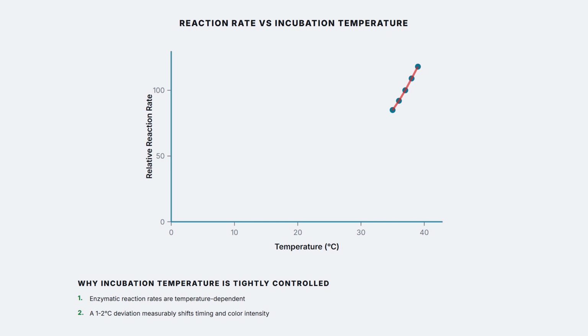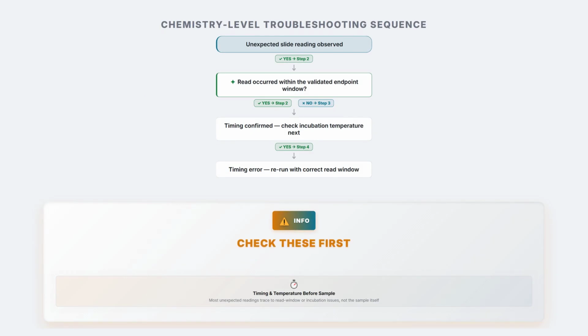Enzymatic reaction rates are temperature dependent, and even a 1 or 2 degree deviation from the validated incubation temperature measurably shifts the reaction's timing and final color intensity. When a slide reading looks unexpectedly off, the chemistry-level troubleshooting sequence starts with timing and temperature before anything else. Confirm the read occurred within the validated endpoint window, confirm the incubation block held its set temperature throughout, and only then move to investigating the slide lot or sample itself.